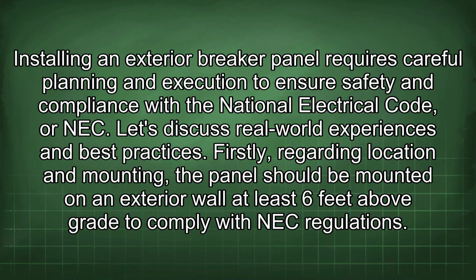Installing an exterior breaker panel requires careful planning and execution to ensure safety and compliance with the National Electrical Code (NEC). Let's discuss real-world experiences and best practices. Firstly, regarding location and mounting, the panel should be mounted on an exterior wall at least 6 feet above grade to comply with NEC regulations.